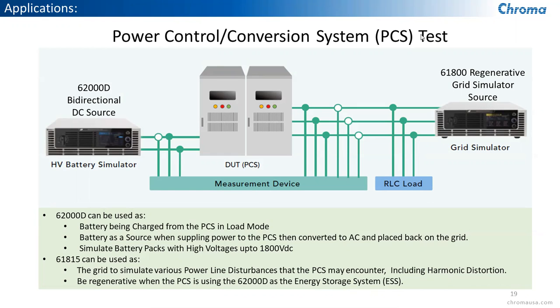Not going to go into a lot of detail, but I just want to highlight that while you're using our 62,000D to simulate your batteries for your energy storage system with your power control and power conversion, you can also use our 61800 regenerative grid simulators. They also operate in all four quadrants. They're regenerative. Whatever power is fed to them from your PCS inverter will then go out to the grid at greater than 80% efficiency.